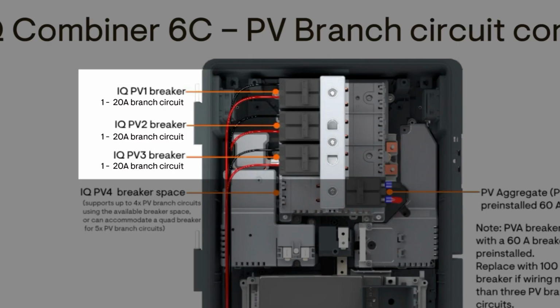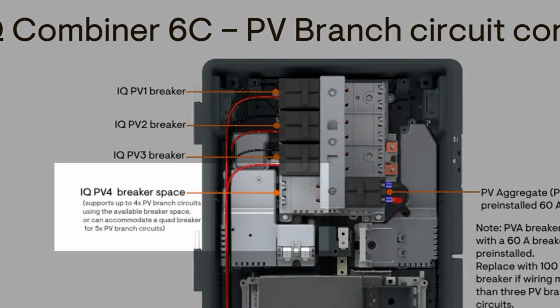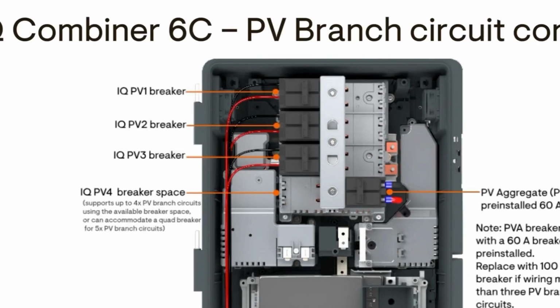A total of 100 amps of solar can be combined into the Combiner 6C. PV slots 1, 2, and 3 can support 3 branch circuits of PV, up to 20 amps of solar each of IQ series PV. PV slot 4 can accommodate another 20 amp branch circuit breaker, or optionally, a 20/20 quad breaker for 2 branch circuits of solar.